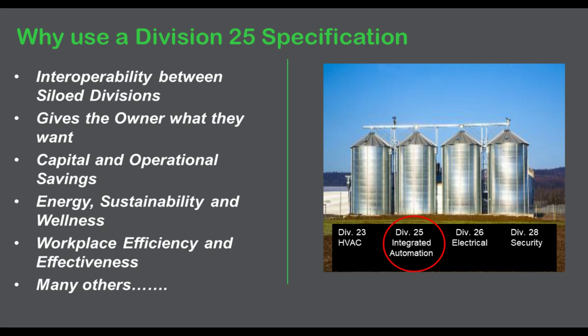There is some capital and operational savings. Obviously, with combining systems, you start to help with coordination. I was working on a project where the entire metering system was all in Division 23. Not that that's an issue, though there are probably better ways of doing it. Nowadays the switchgear is much more intelligent, even down to the breaker level, including monitoring KW and KWH at the breaker level. So there's no reason not to make an intelligent switchgear or panel that can just be connected, since there's no reason to put downstream meters when you can do it upstream at the source in a lot of cases.